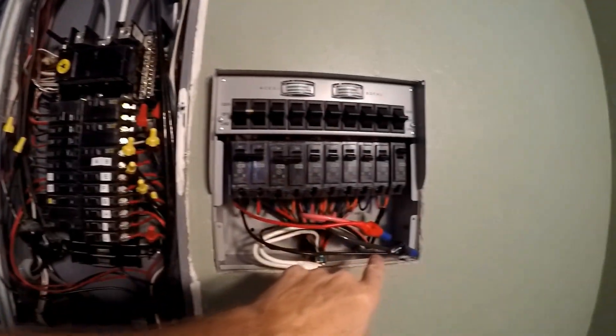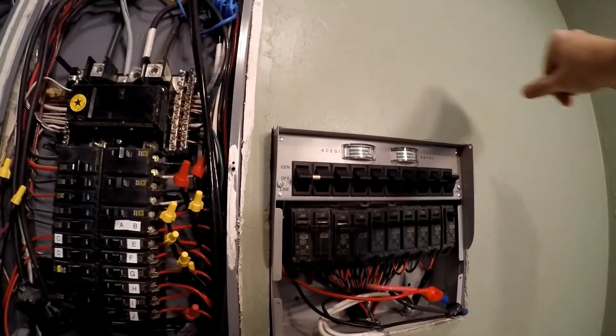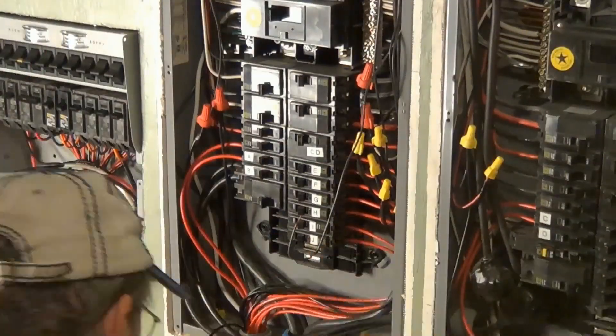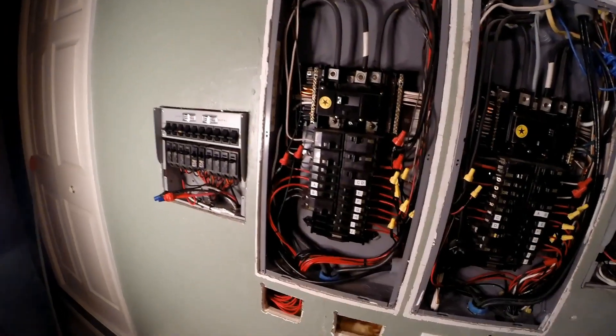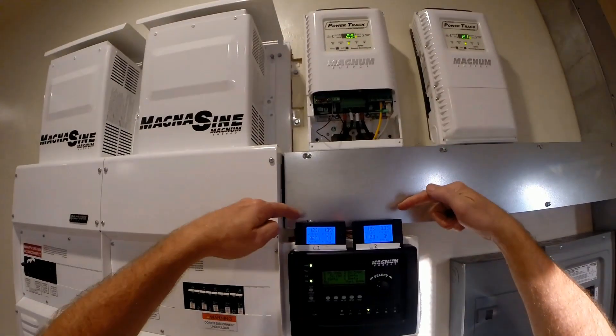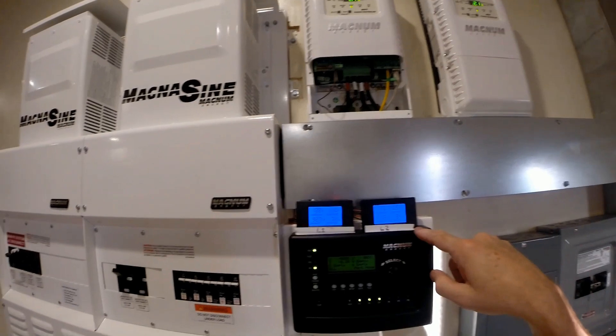This transfer switch is powered by the utility and by the solar, so I should be able to switch to line or to gen — look at that! So I got this side all wired up. Today I'll show you what it looks like all buttoned up. These two are for the L1 channel and the L2 channel.